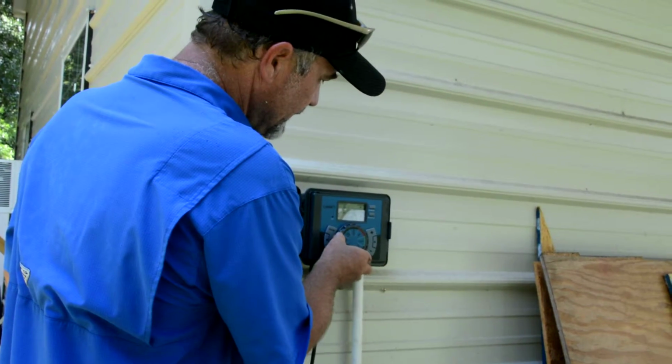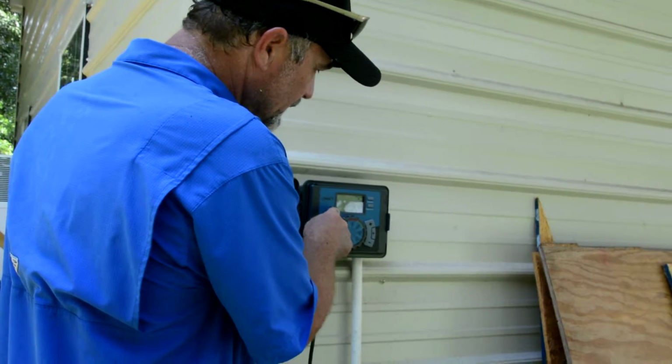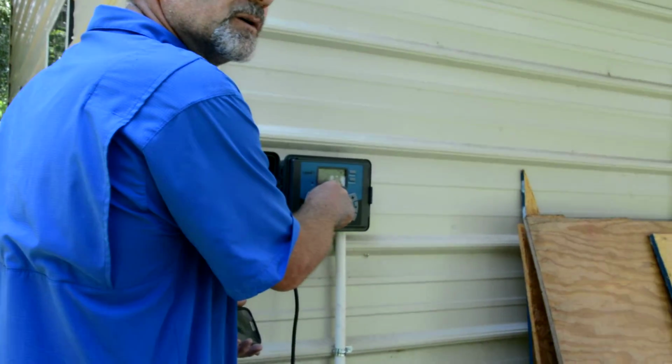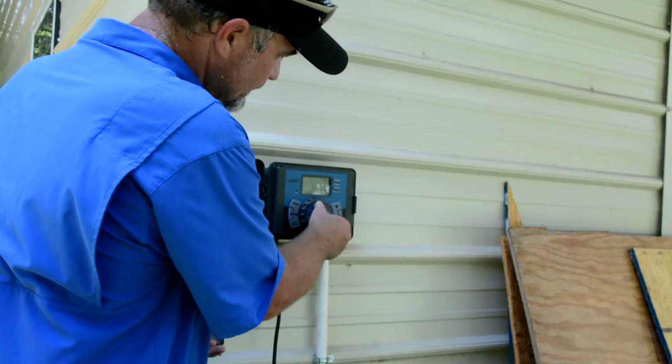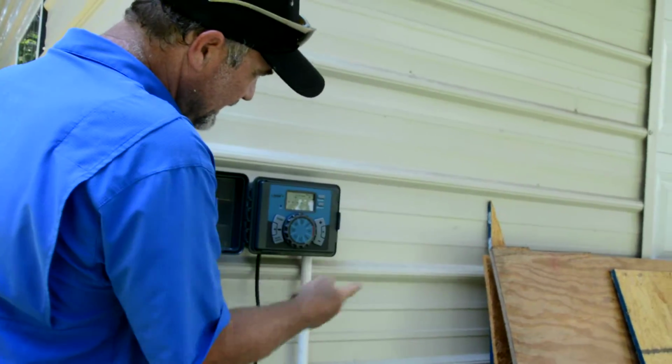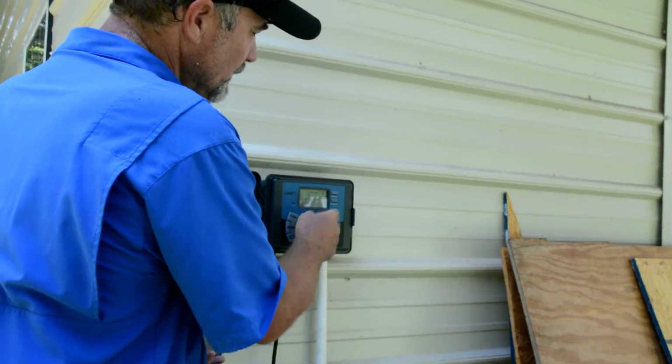Then we're going to come over here on how often on program B. And we're going to set all of these days to water, because we want it every day. Every day. Then we're going to come over here to our start time on program B again. We're going to set a start time.